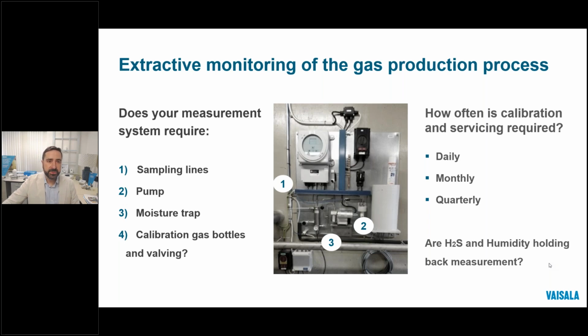This can pose challenges in cold climates where the condensate can freeze and clog lines, requiring heated enclosures and heated lines, like I mentioned. The separate enclosure requirements are also due to the fact that these analyzers are not EX certified for the Class 1 Div 2 or ATEX Zone 0-1 environments at many plants.